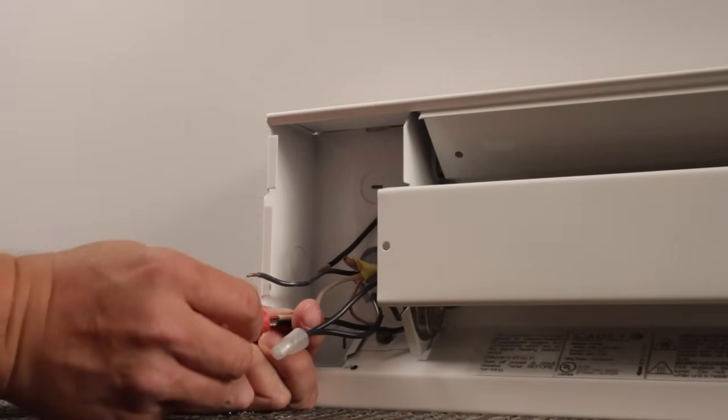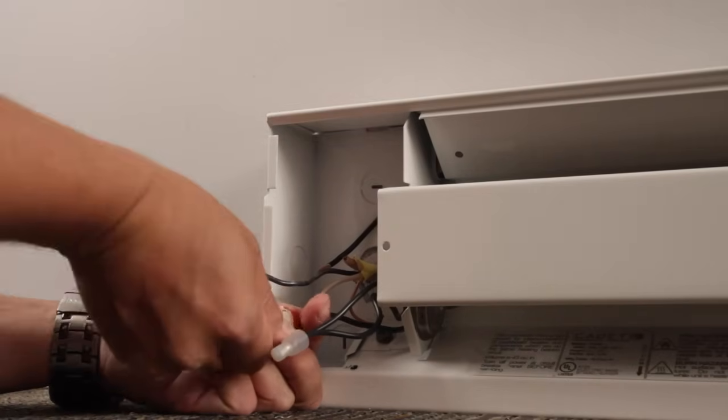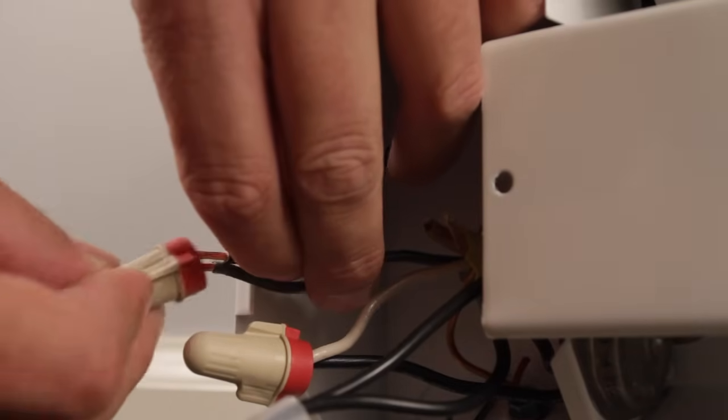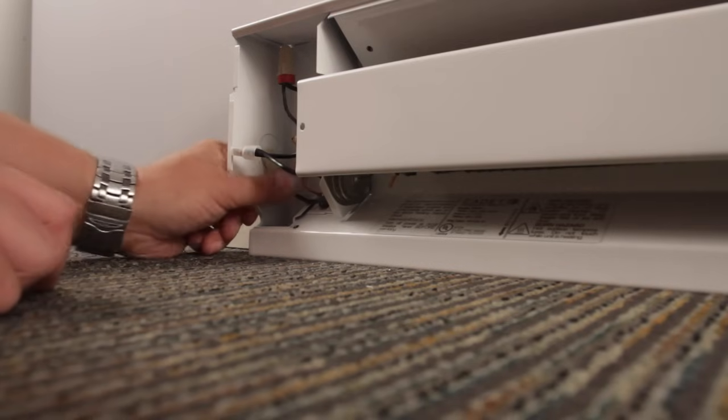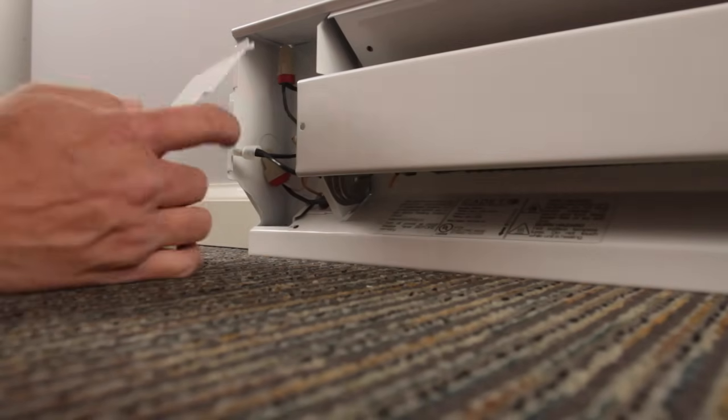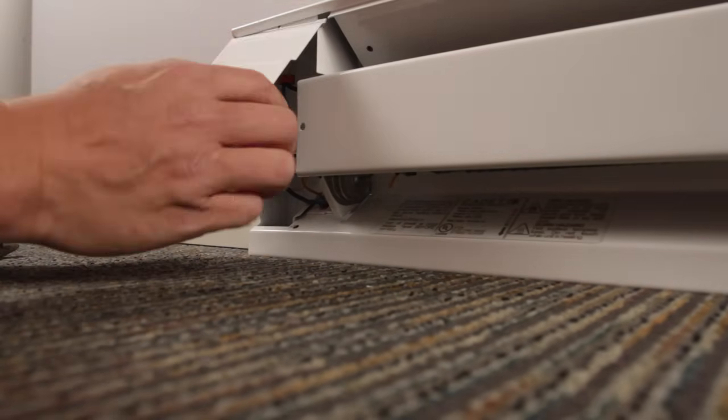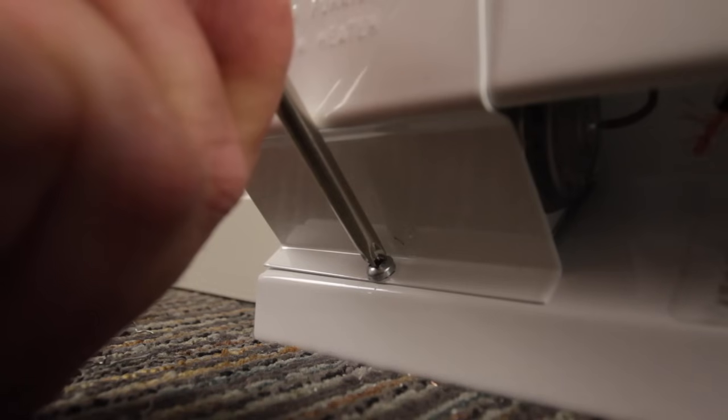Connect one black wire from the heater to the white wire from the wall. Now connect the last black wire from the heater to the black wire from the wall. Safely tuck all wires in the heater wiring compartment and attach the cover plate with the provided screw.